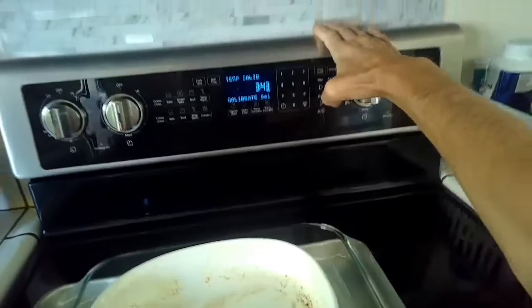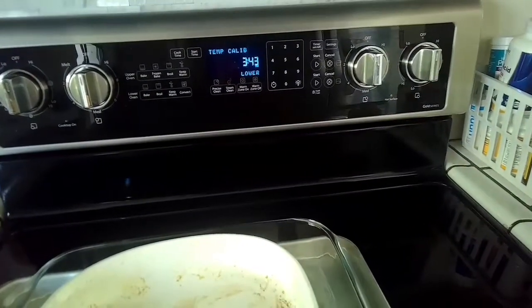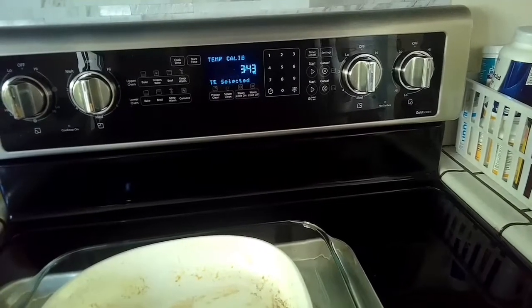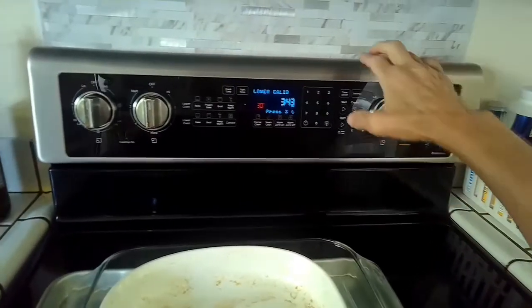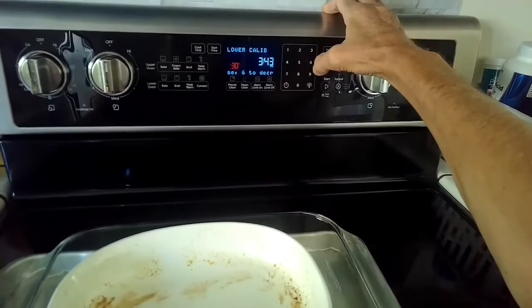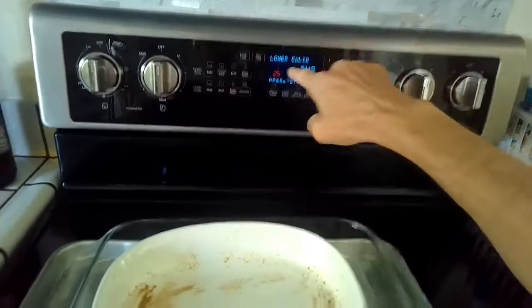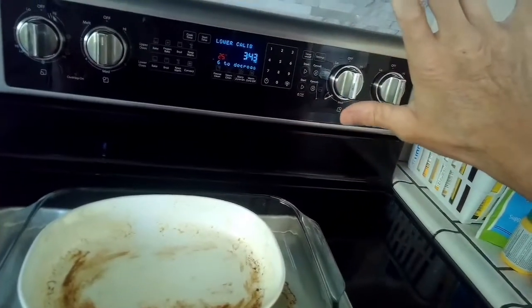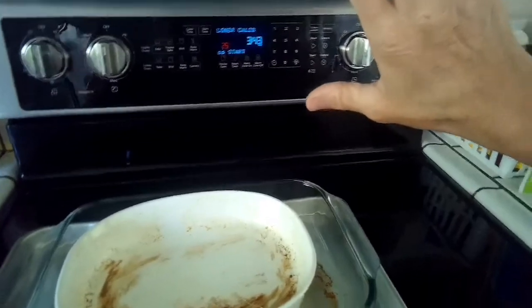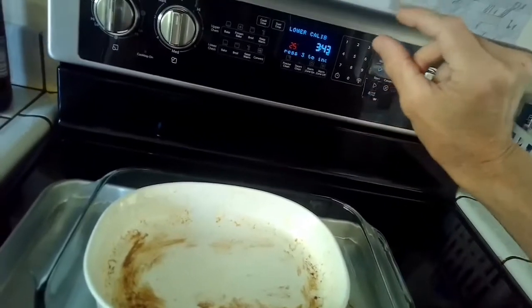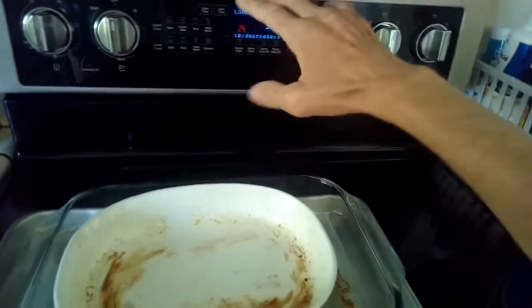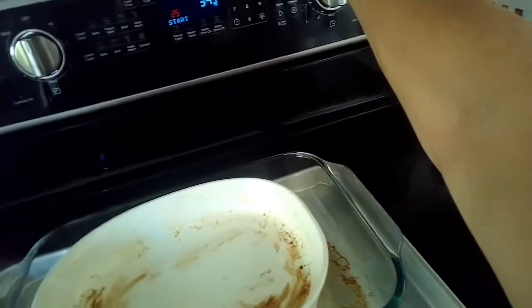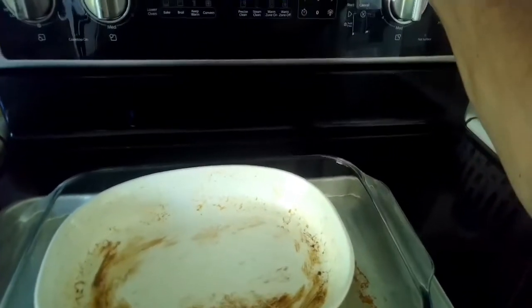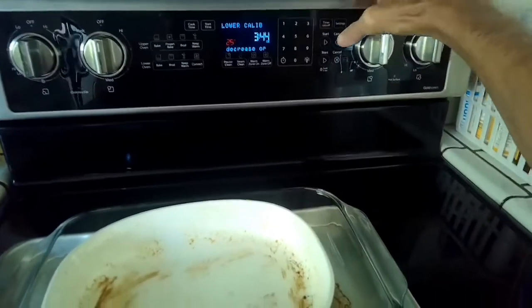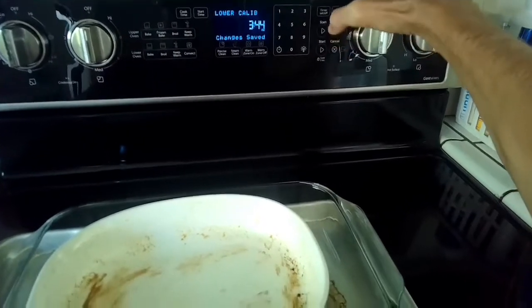Press 1 for upper. Okay, so I want lower, so I'll press start. It's saying you did select the lower one, and then it's going to give me a chance to tweak the temperature a little bit. If I press 6, I can do a decrease. I'm going to go 6, and I just brought it down from the 30 degree change that I had previously. I tried to get 30 degrees higher than normal, which got me, instead of 350, about 355. By pressing 6, it let me decrease it by 5 degrees, which gives me now 25 degrees above what it was thinking before. So theoretically now it should be exactly at 350. So what I'll do now is press start, and changes are saved.